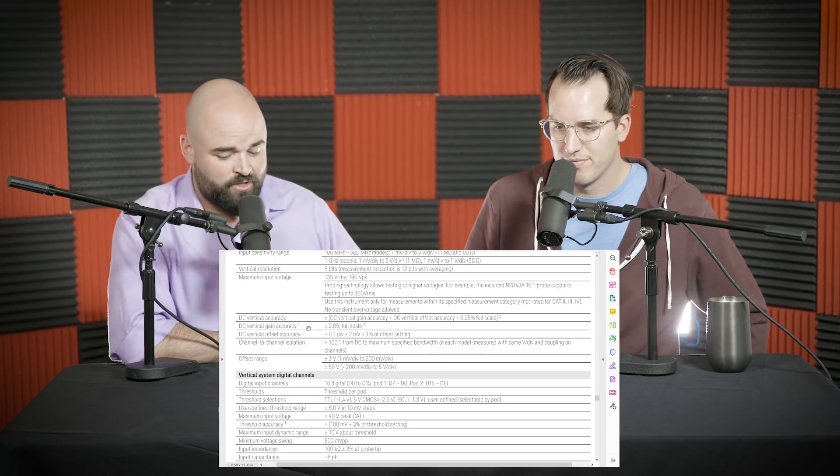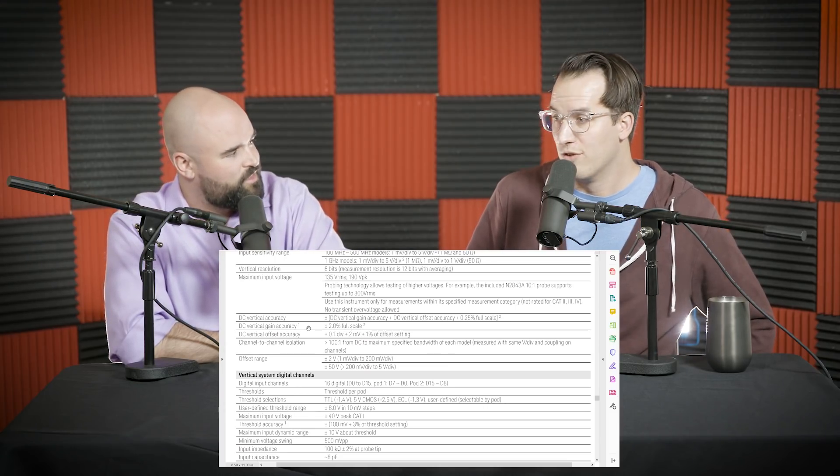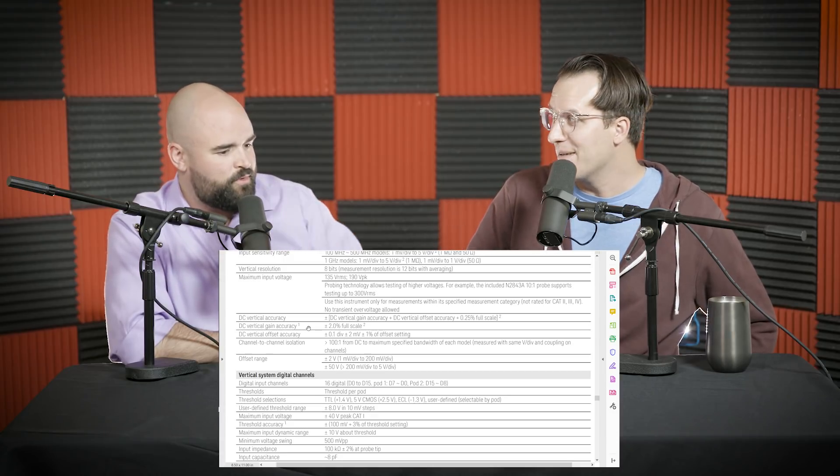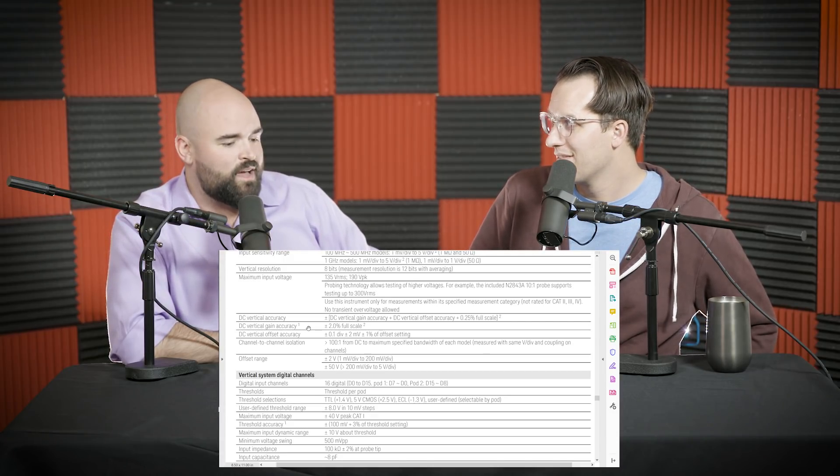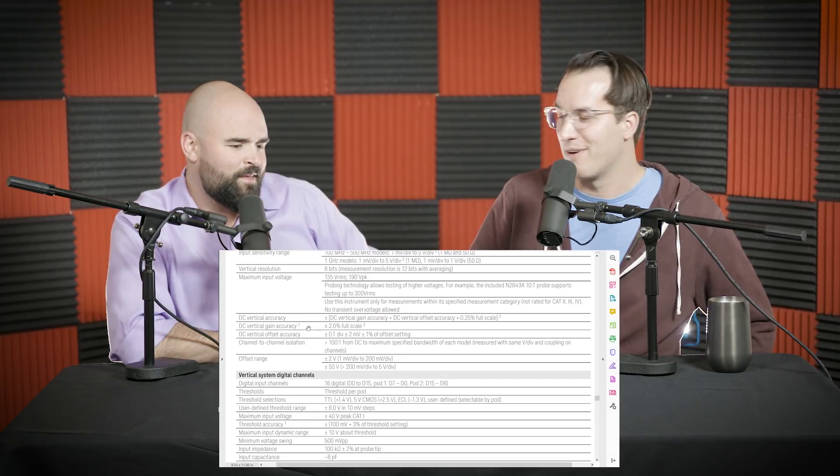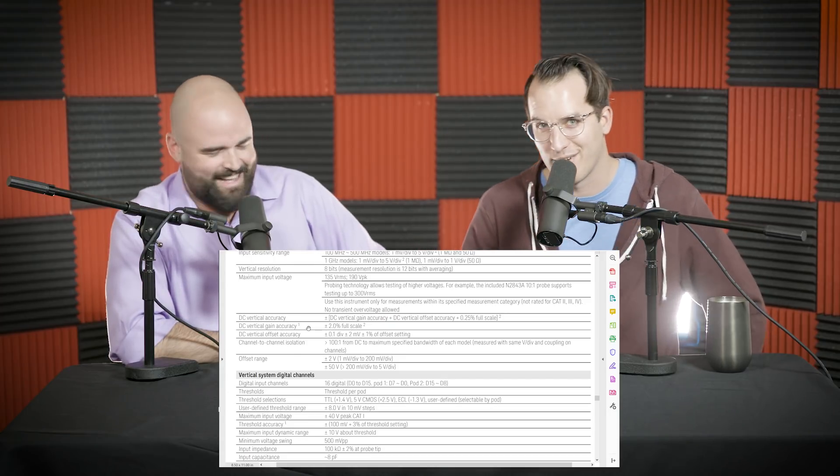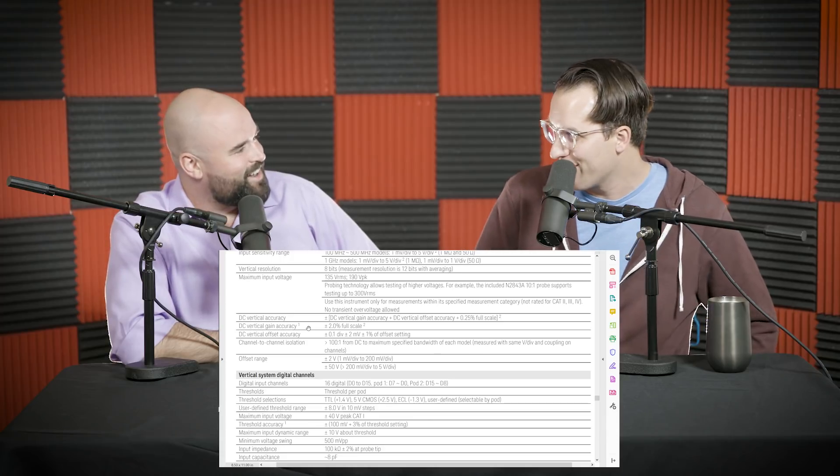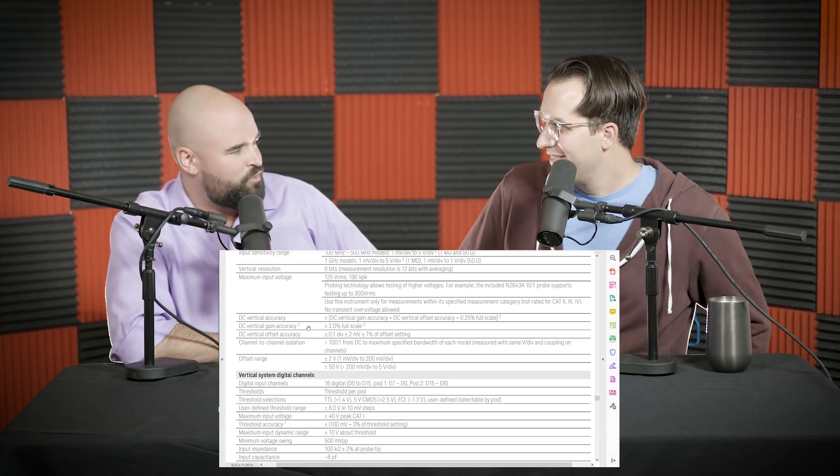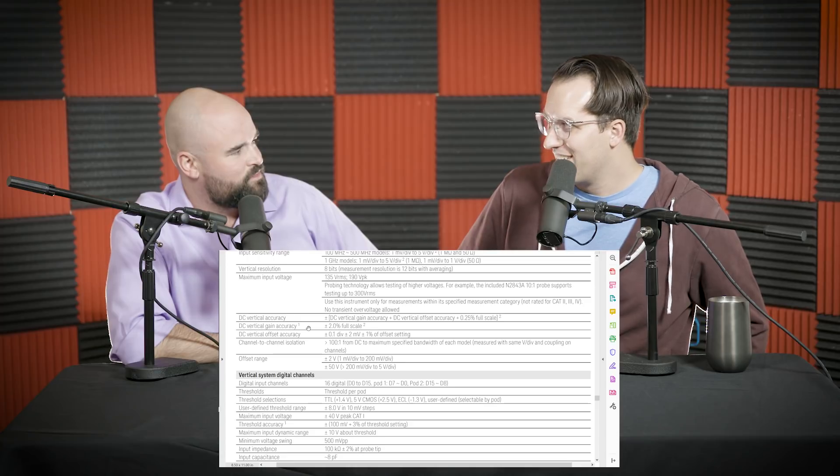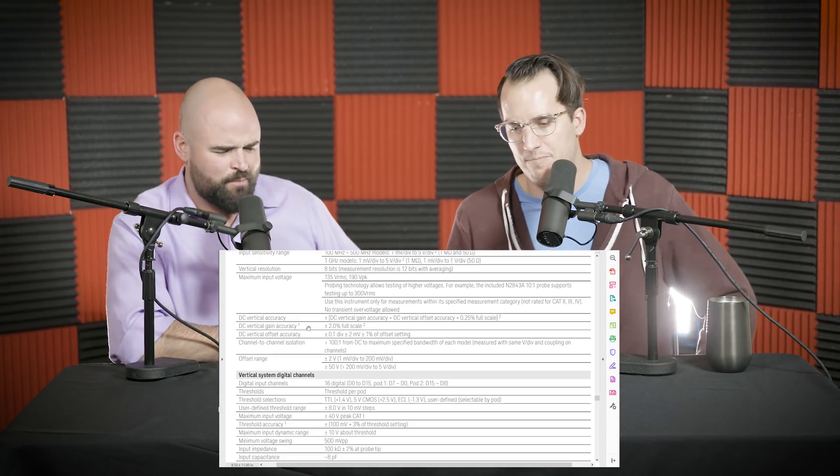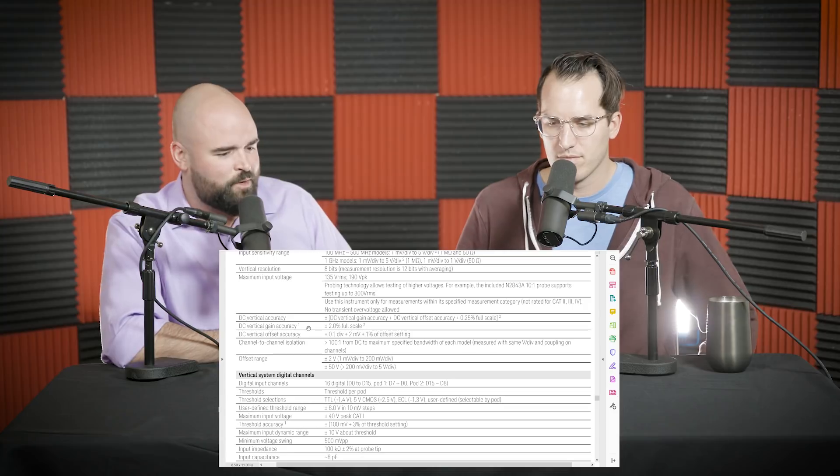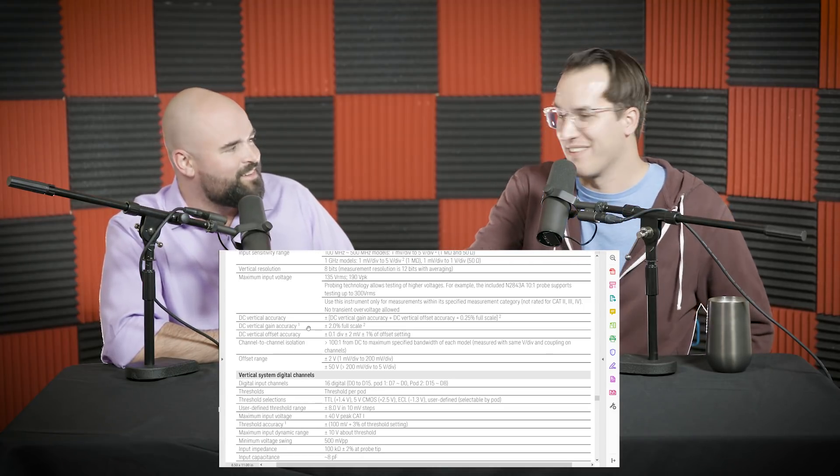DC Vertical Gain Accuracy, right here, this line item, 2% of full scale after warming up for 30 minutes. That's the warranted spec for a DC input signal. I know this from my support days. I had like a form email that I sent when I got this question from the new support reps. People hit us up all the time, like, hey, I want to use it as a multimeter, basically. I'm like, buy a multimeter.